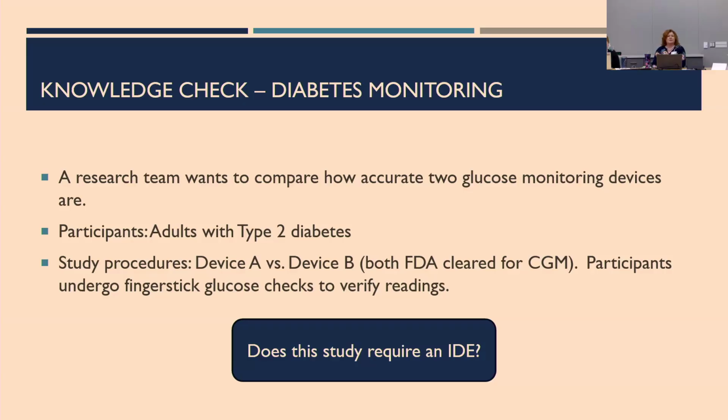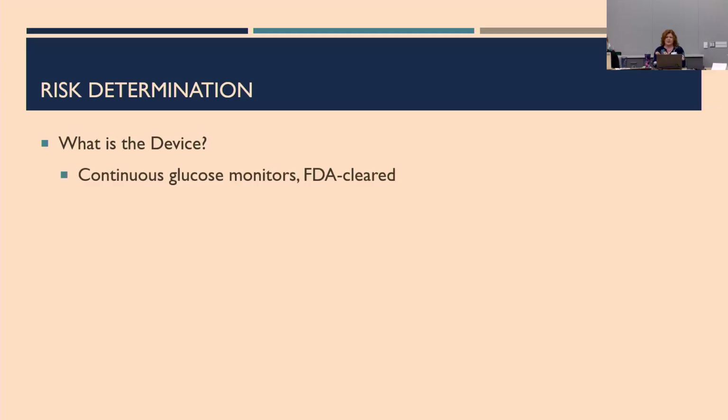So 71% say no, an IDE isn't required, and 29% say yes, an IDE is required. I guess I probably should have specified whether this is an abbreviated or a full IDE as well. So let's walk through the risk determination for this one. So what is the device? It's the continuous glucose monitors or CGMs that are FDA cleared.